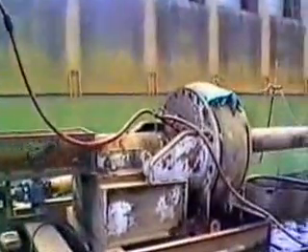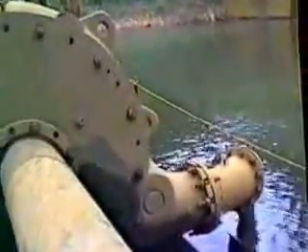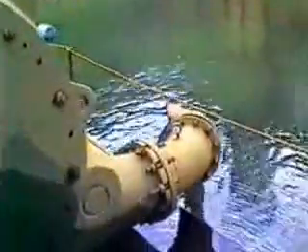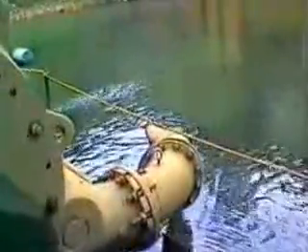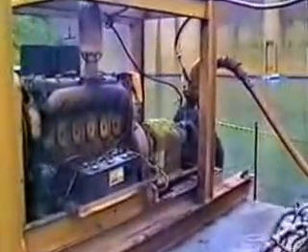It required about 80 PSI to get the solids through the pipeline. Here is a 170 horsepower diesel-driven jet water pump. It provides the jetting water for our DP-150 pump at 500 gallons a minute and 80 PSI.